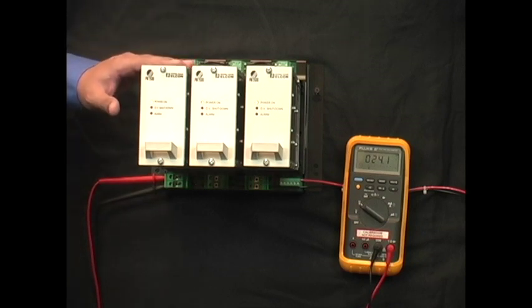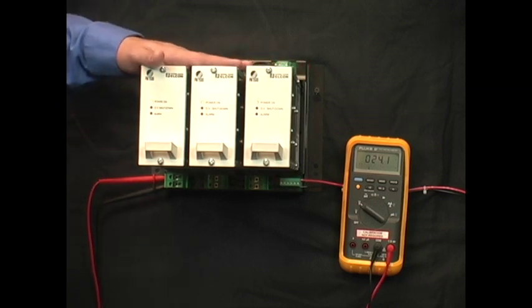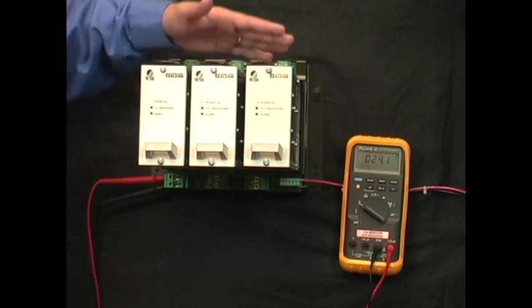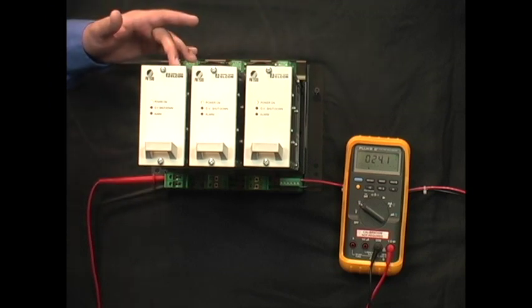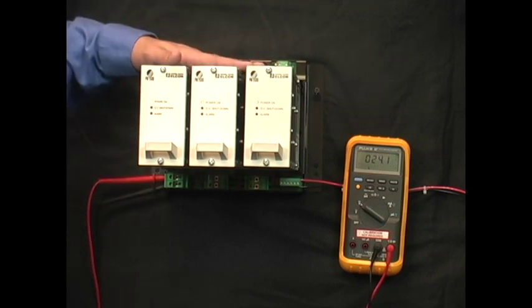These are N plus 1 redundant power supplies, so you have a series of power supplies working for one load. With N plus 1 configuration, you can have any one of these power supplies fail and still be able to power the load.